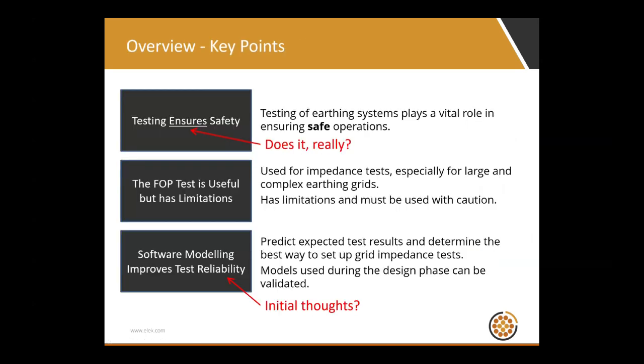Overview of the key points. Testing ensures safety. Testing is a very important step in earth grid design. It plays a vital role and ensures safe operation post installation and commissioning. We almost always will do a current injection test or a fall of potential test or both. It's questionable though. Does it really ensure 100% safety? That's a question mark for you.